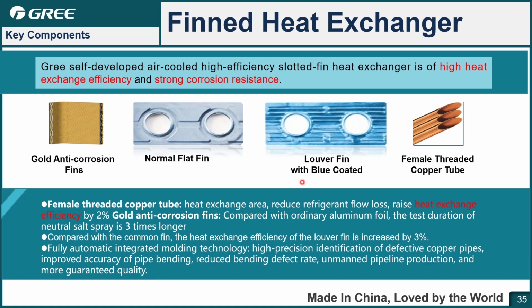For the heat exchanger, first we apply some anti-corrosive painting on the fin and the condenser of the outer unit, so it looks golden. And also for the fin we choose the louver fin with blue coating. For this kind of fin, the heat exchanger efficiency is higher than the normal flat fin. And also for the copper pipe, we choose the female threaded copper pipe, also with higher heat exchange efficiency. So by this design, we can keep the unit running in a very good status, even in a corrosive situation, and also make sure the heat exchange of the unit is good to get a better capacity.